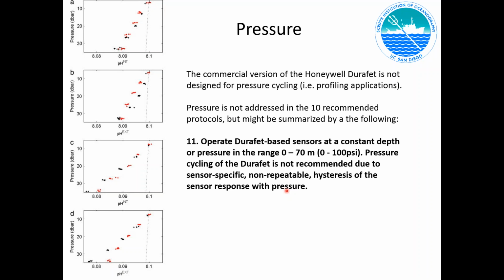So the short story here is that we see a different pressure response for each sensor, and we've also seen it to be hysteretic. And since at this point no one is regularly, systematically characterizing the pressure effect on the stock Durafet sensor, it's not a good idea to use them for pressure cycling in the sense of carrying out ocean profiles. Even though the sensors can operate up to 70 meters, it's not recommended to take a Durafet sensor and do 0 to 70 meter profiles with it.